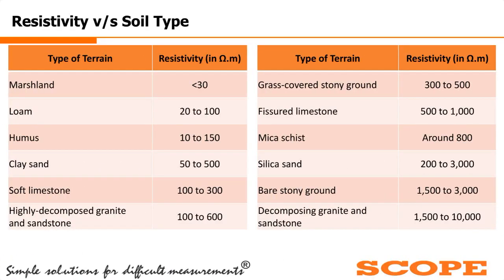Now, these are some values used for the different land types or soil types. These values are given in various IEEE standards, and we are just giving you some figures of resistivity for different types of terrain. For a marshland type of terrain, the resistivity is generally below 30 ohm meters, and it can go up to 1500 or 3000 for earth surfaces where there are stones or sandstone. Then the soil resistivity may go even above 1500. So these are some values mentioned depending upon the earth type.